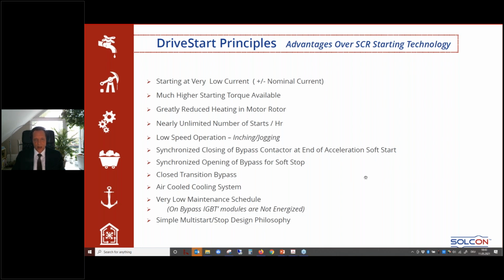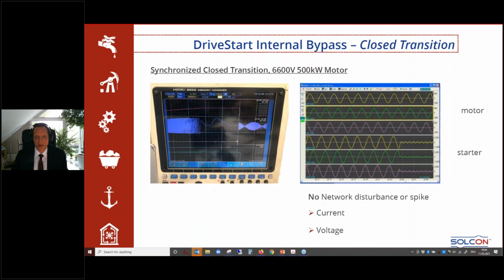Closed transition, it's an air-cooled system, and we give you all the values that are needed for sizing the AC in the switchgear room, but it's usually not much because you have the losses only during the starting period, which is usually less than 1 minute, and that's it. Low maintenance schedule on the bypass. When the bypass is on, the IGBT modules are not in operation, and we also have a simple multi-start or stop design philosophy.